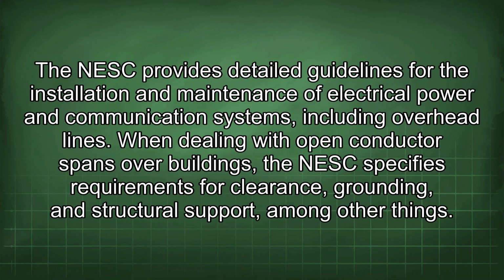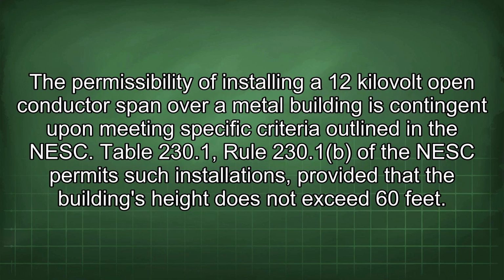The NESC provides detailed guidelines for the installation and maintenance of electrical power and communication systems, including overhead lines. When dealing with open conductor spans over buildings, the NESC specifies requirements for clearance, grounding, and structural support, among other things. The permissibility of installing a 12 kilovolt open conductor span over a metal building is contingent upon meeting specific criteria outlined in the NESC.